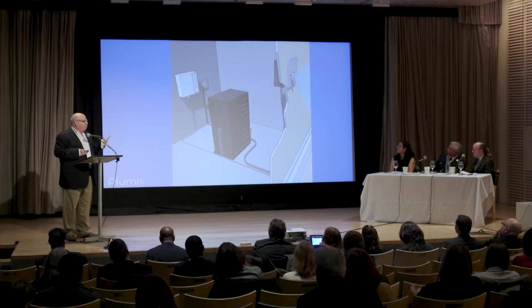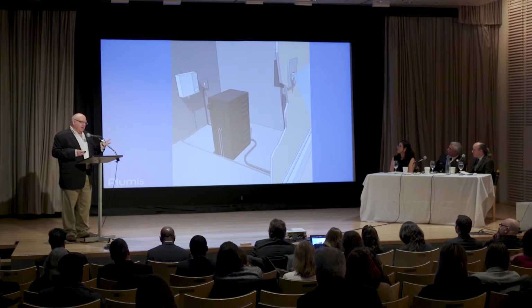So this is a pre-engineered dry pipe water mist system. Pre-engineered means we've already done the engineering for it. We are able to put this, and it will cover a radius of about 20 feet for each head. So if you have a larger space to fill, you put a second head in. Dry pipe means that the water is not in the hose. The water comes up to the pump, and that's where it stops. There's a double valve in the pump system so that there's no water that goes by and no water can come back. Goes through the high pressure pump when needed.